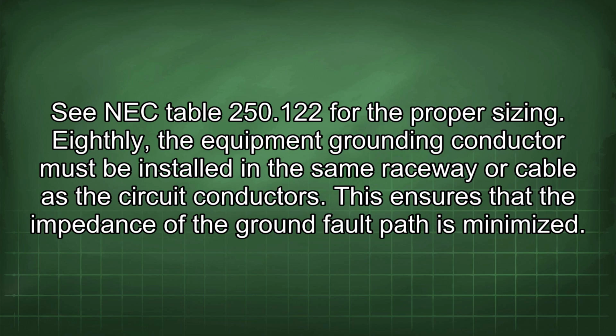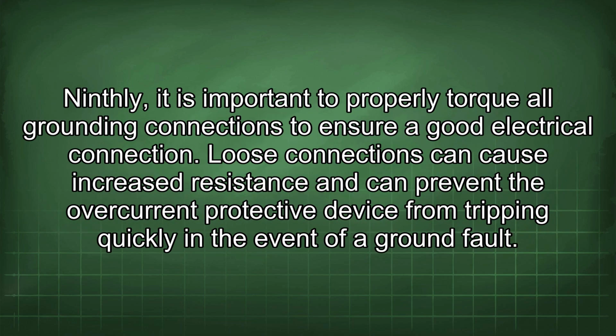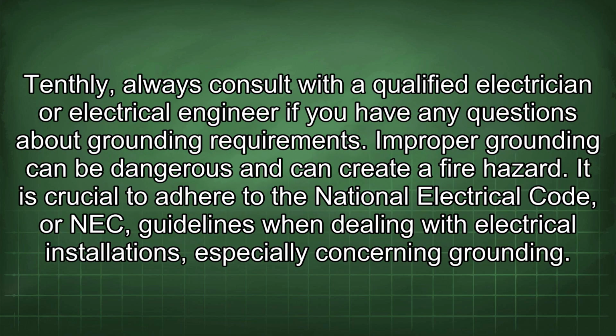Eighthly, the equipment grounding conductor must be installed in the same raceway or cable as the circuit conductors. This ensures that the impedance of the ground fault path is minimized. Ninthly, it is important to properly torque all grounding connections to ensure a good electrical connection. Loose connections can cause increased resistance and can prevent the overcurrent protective device from tripping quickly in the event of a ground fault. Tenthly, always consult with a qualified electrician or electrical engineer if you have any questions about grounding requirements. Improper grounding can be dangerous and can create a fire hazard.